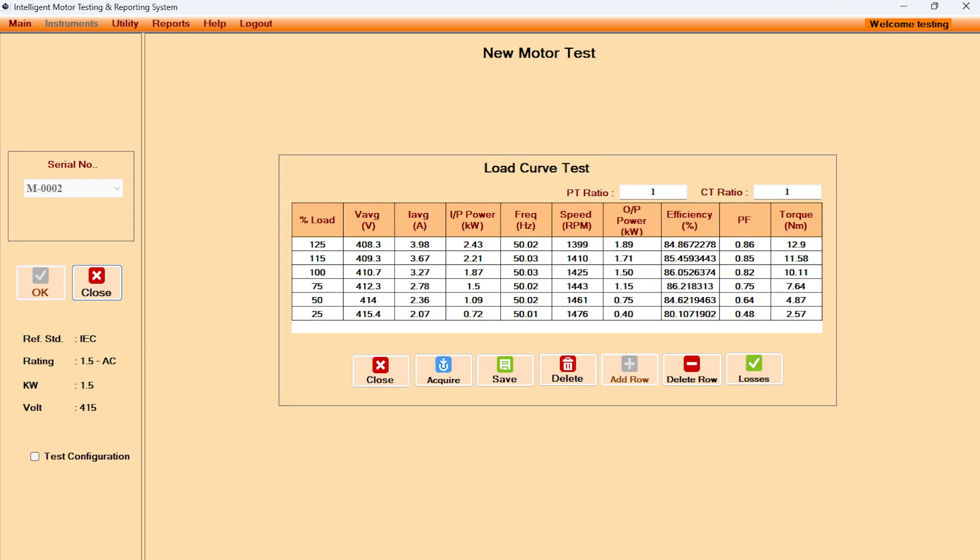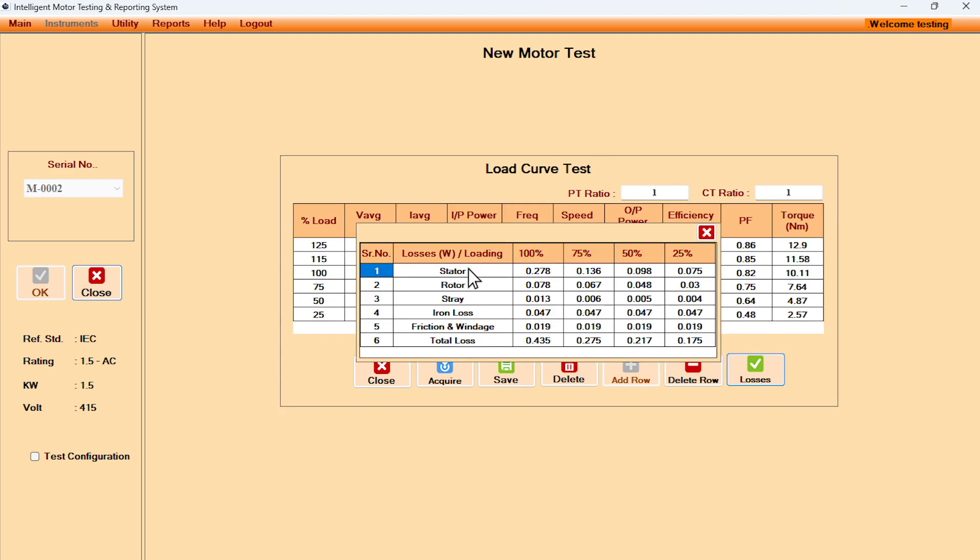In a motor load test setup, while conducting load curve test, at various loading percentages, efficiency and torque measurements are displayed automatically. Instantly, losses for stator, rotor, stray loss, iron loss, friction and windage, and total losses at various loading percentage are populated.